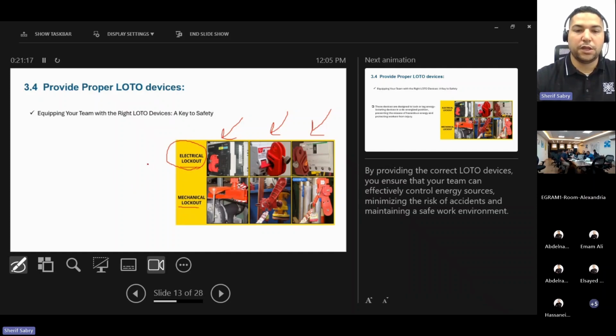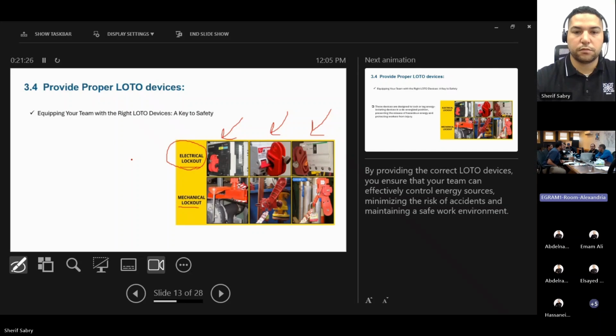But what about the effectiveness of these equipment? Yeah, it works well with us. After we isolate with this type, we test if there is voltage at the machine or not, and if there is no voltage, then it works properly for us. Yes, it's important to stop and verify when implementing LOTO, because you need to lockout tagout and then make a tryout. This step you mentioned is the most important step in implementing LOTO. It's very, very good.